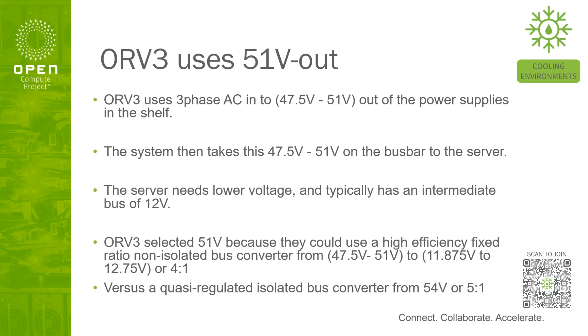As you can see here, for ORV3 the power supply spec today is 47.5 to 51 volts. That came about because in OCP, when they were running 10 to 12 kilowatts, they found the efficiency in the server was better for the DC to DC conversion. Now, when you start moving up to 50 kilowatts and more in fluid, like we're trying to do, I suggest we look at 54 volts.